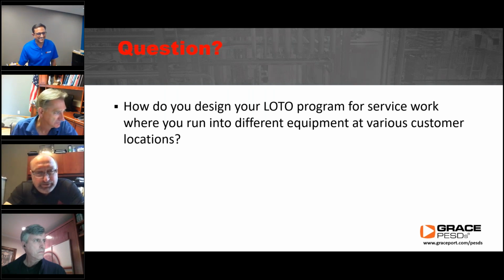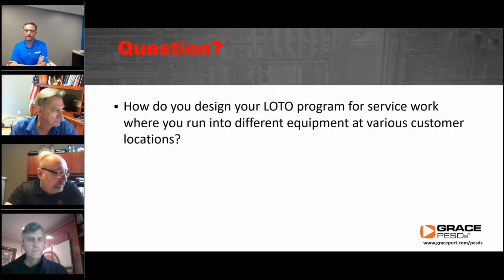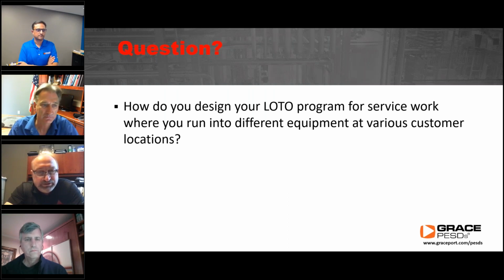Well, when you read it, your occupational health and safety management system and the related lockout tagout program policy is generically applied against all workplace hazards. So I'm a bit confused why there should be a difference in how your lockout tagout program is applied at different locations for different customers. If you look at Article 120 in NFPA 70E, it's generic lockout tagout content — it's about what energy source you're isolating. There should be an energy isolating device, and you follow the requirements of your program with individual lockout or group complex lockout. Your lockout tagout program is generic and applied against not only electrical energy but all energy sources generically.